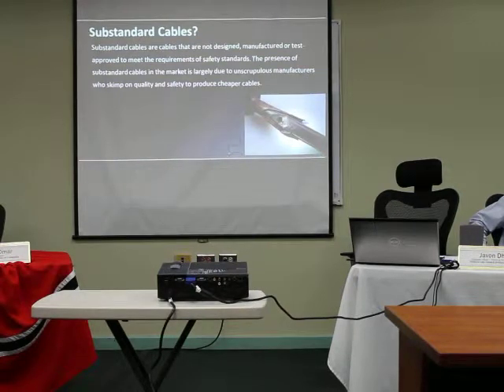Substandard cables are cables that are not designed, manufactured, or tested and approved to meet the requirements of a safety standard. The presence of substandard cables in the market is largely due to unscrupulous manufacturers who skimp on quality and safety to produce cheaper cables. When we speak about unscrupulous manufacturers here, we're talking about the international arena.